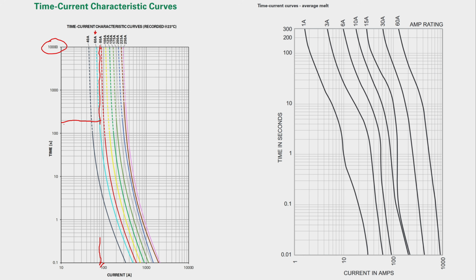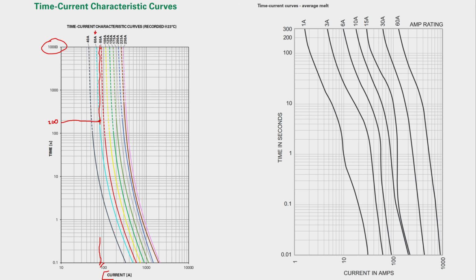So if I use a 60 amp fuse and the load current is 80 amps, it'll take 200 seconds for that fuse to melt, because that's where the melting line crosses over the load current line. So we can see that even a 60 amp fuse is going to take more than 2 minutes to fuse at the 80 amp load current. So we can see that we have to look at these curves to specify the right fuse size.